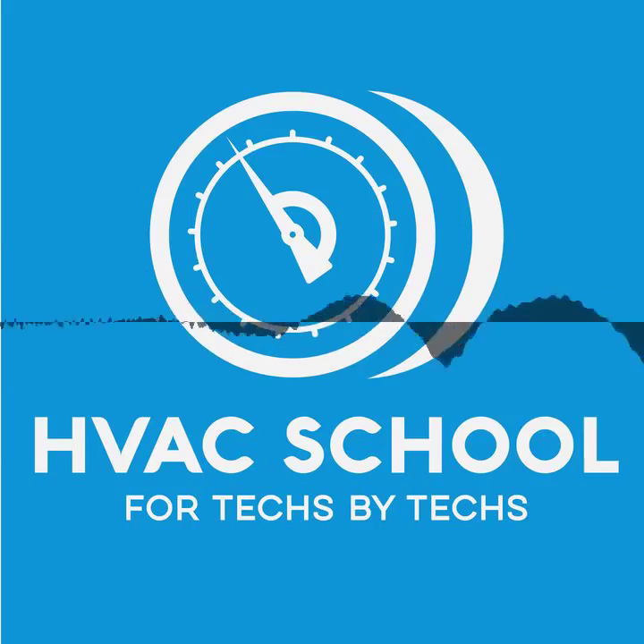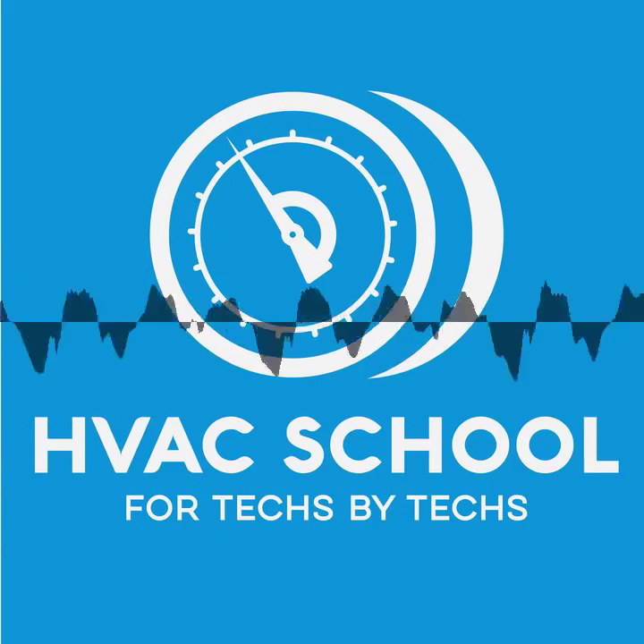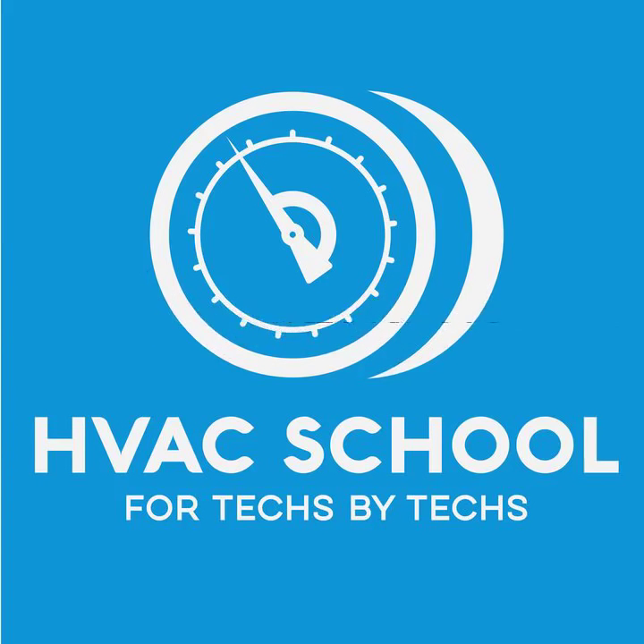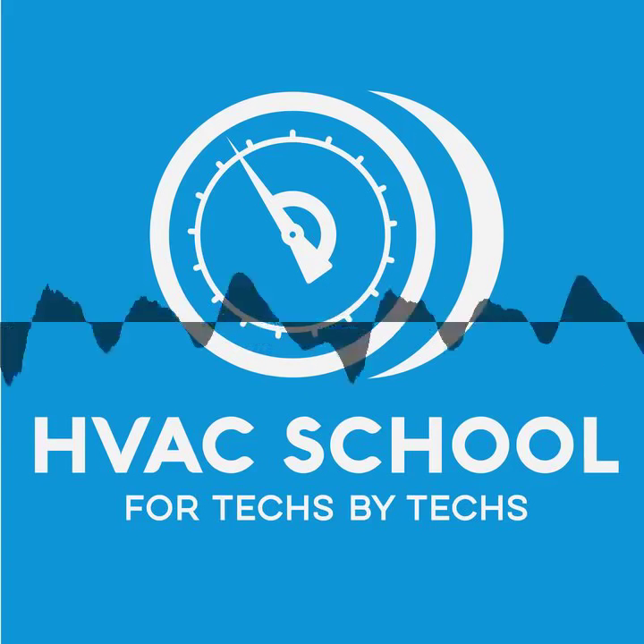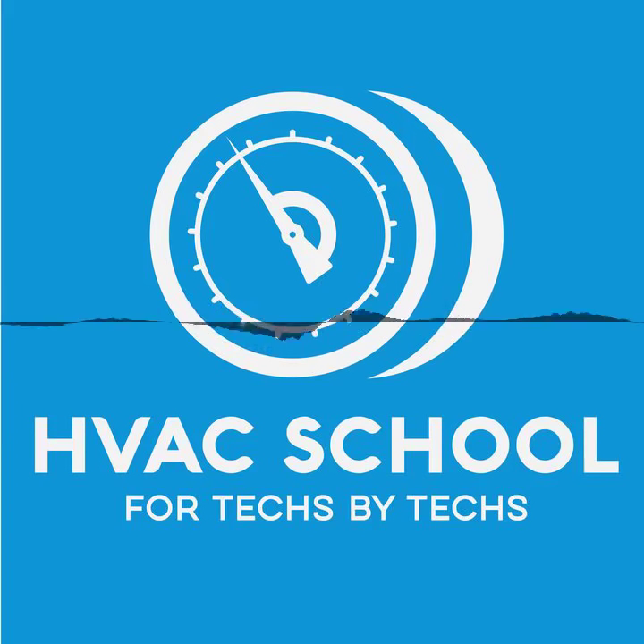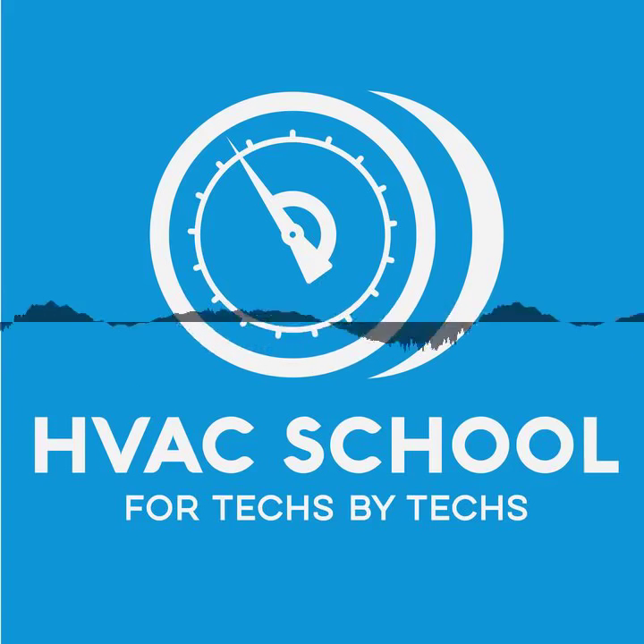So the interesting products. But today we're here to talk about Delta T. And so Delta T is often called, in fact, I never called it Delta T when I first started in the business. I used to call it an air temperature split or a temperature split. We would say, what's your temperature split? And the idea in our market was that it should be around a 20-degree split in cooling, which means that your return air coming over the evaporator coil, so the air entering the evaporator coil, should be about 20 degrees warmer than the air leaving the supply coming out of the top of the unit.